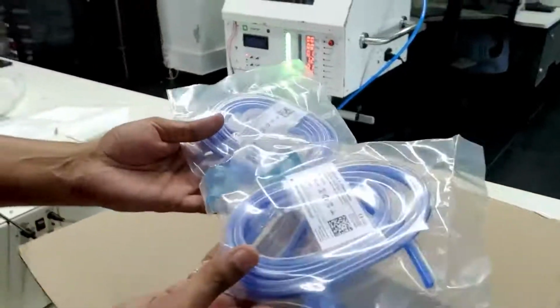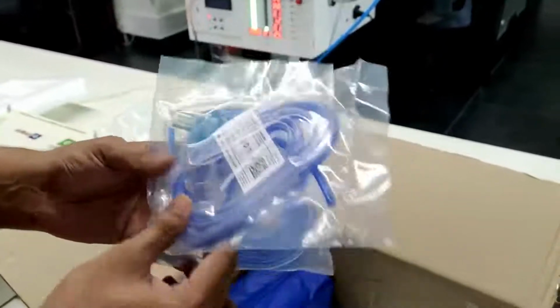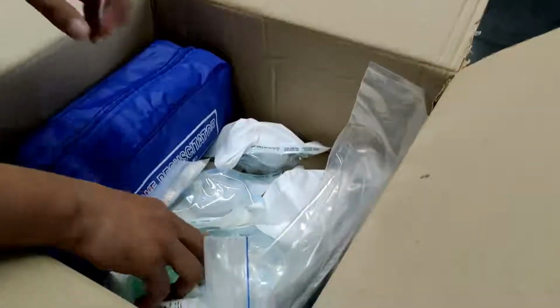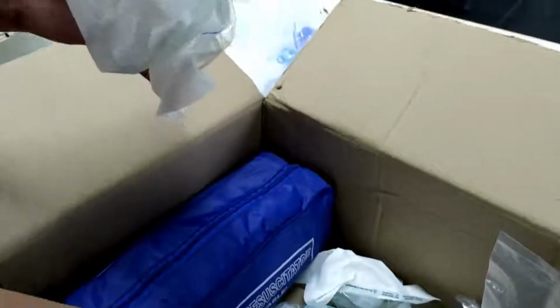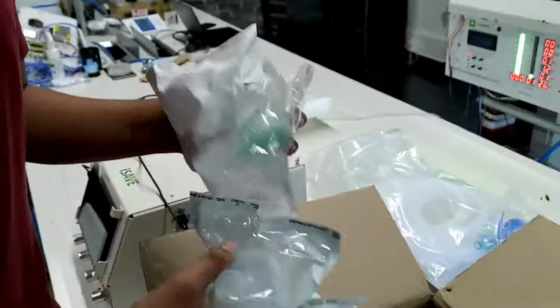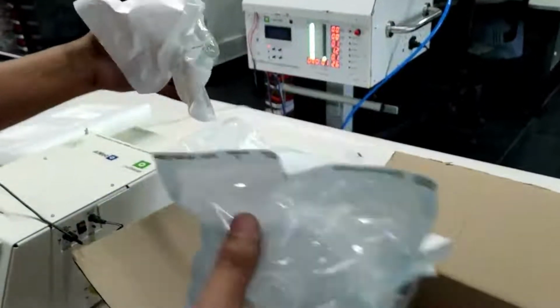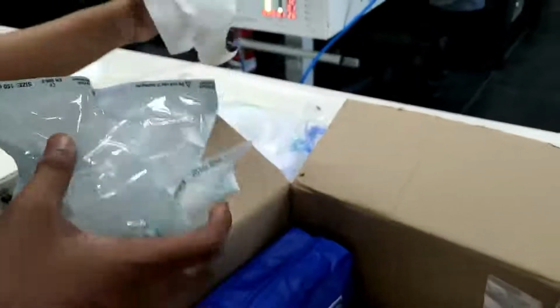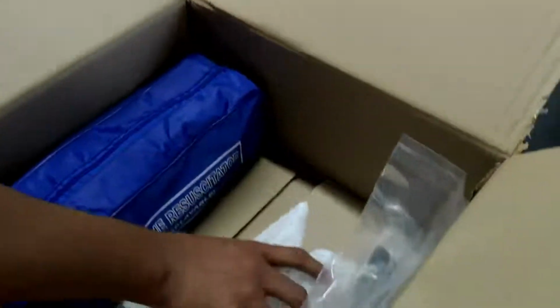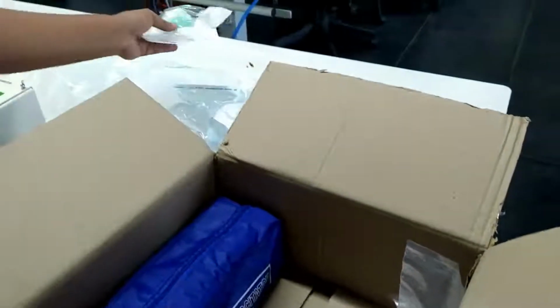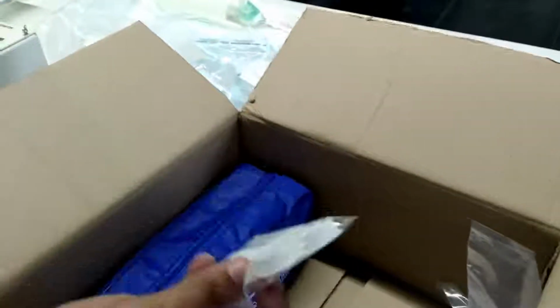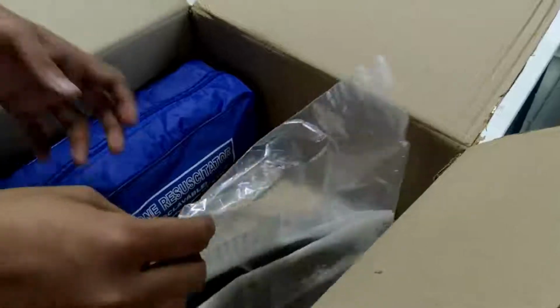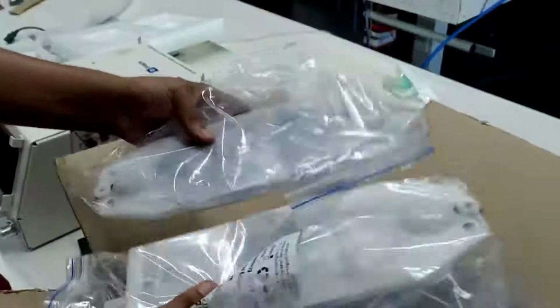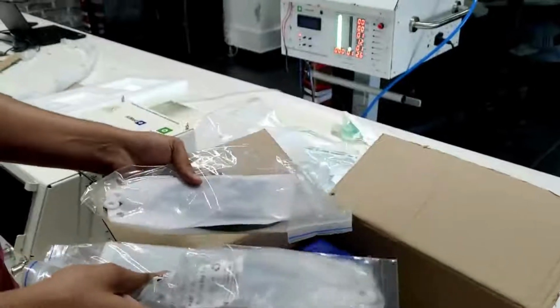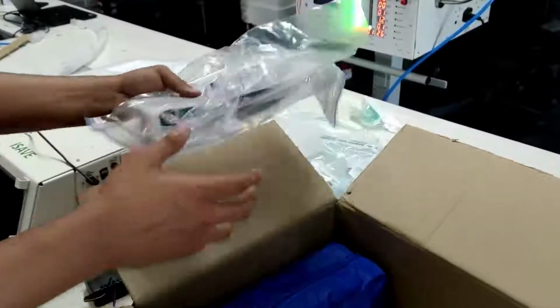We have additional flow sensors, the Venturis. So there are two of those. We have a couple of HME filters and CVF filters so that the inside of the system doesn't get contaminated, or there's no cross-contamination happening or goes into the air or anything like that. So put that to the side. We have caps for closing the ports that's needed. We have two patient lungs, so this can be used to test the device to see if there's anything wrong. Put that to the side.